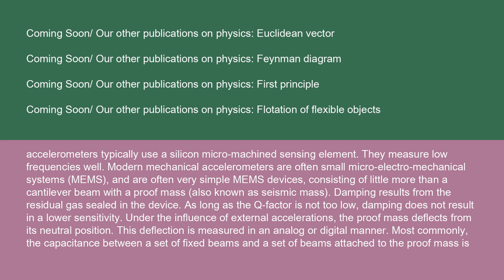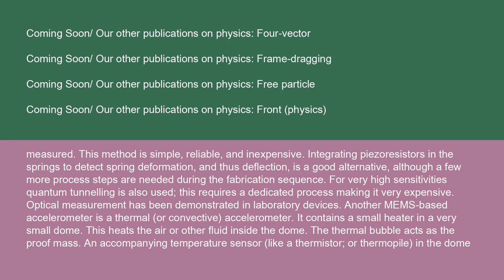Modern mechanical accelerometers are often small micro-electromechanical systems (MEMS), often consisting of little more than a cantilever beam with a proof mass, also known as a seismic mass. Damping results from the residual gas sealed in the device. As long as the Q factor is not too low, damping does not result in lower sensitivity. Under external accelerations, the proof mass deflects from its neutral position; this deflection is measured in an analog or digital manner — most commonly, the capacitance between a set of fixed beams and a set of beams attached to the proof mass. Integrating piezo resistors in the springs to detect spring deformation and thus deflection is a good alternative, though a few more process steps are needed during fabrication.